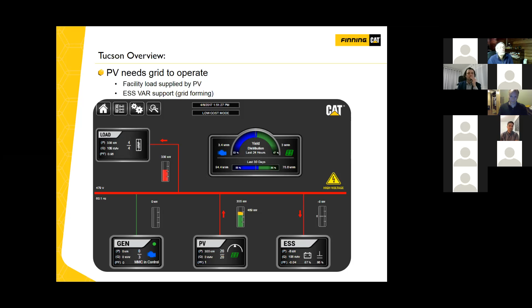In this diagram, you can see the flow of energy being created in the PV in the middle there, flowing 100% to the load, and also doing a little bit of charge on the batteries. However, if you look very closely at the batteries, you can see that there's a large kVAR reaction coming from the batteries, because it is setting the power factor, for all the electrical people on the call. So it is very important to have another source on there when you're a remote site, such as batteries, or you would be running that diesel generator most likely at a low load. You can go to the next slide now, Sid.